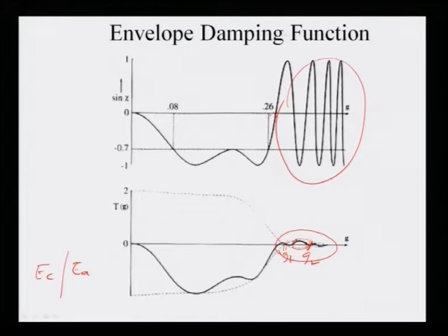Obviously, the first thing one can do is this: the worst case of constant transfer function is when the transfer is minimized, that is, you just start defocusing the objective lens in such a way that you do not see any contrast on the screen, or on the computer screen, or on the fluorescent screen. If you do not see that, that becomes your reference. From that you start changing the focus value and reach the Scherzer defocus value. So, this minimum value here, as you can see, corresponds to this number of sin psi, and this number of sin psi happens to be 0.7.